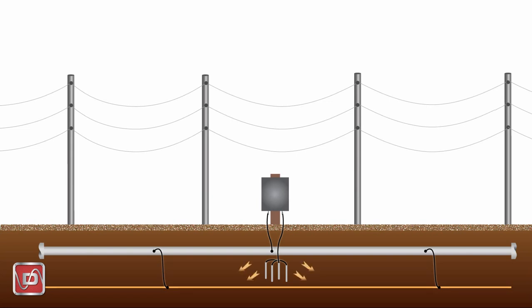By installing a zinc ribbon and connecting it directly to our pipe, we've also made the zinc ribbon part of our cathodic protection system. Our cathodic protection system will be significantly impacted, trying to protect the zinc as well as the pipe.